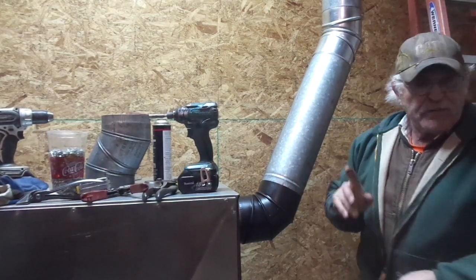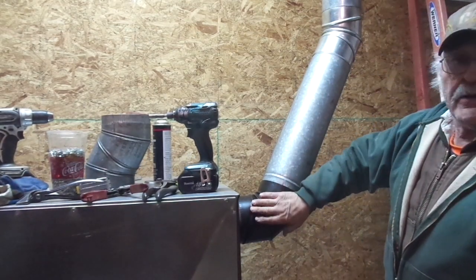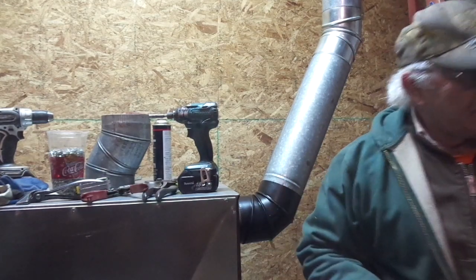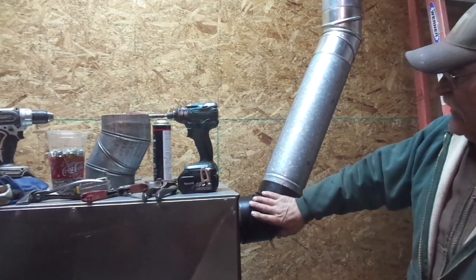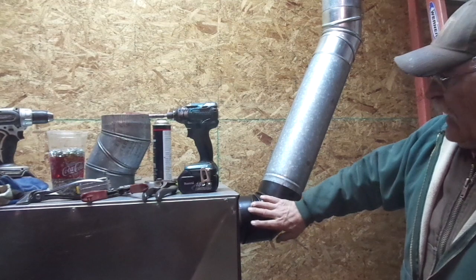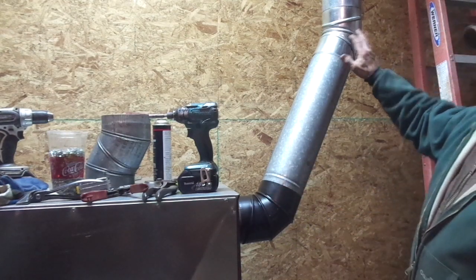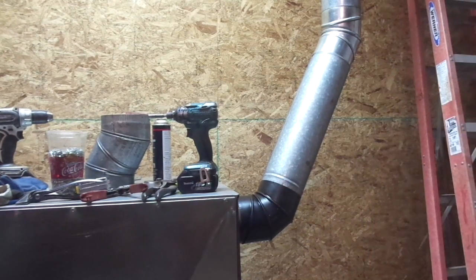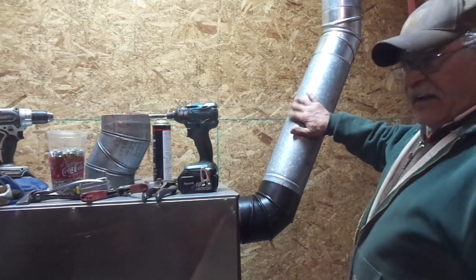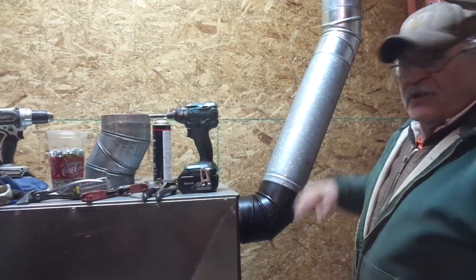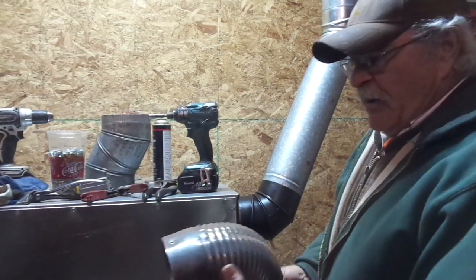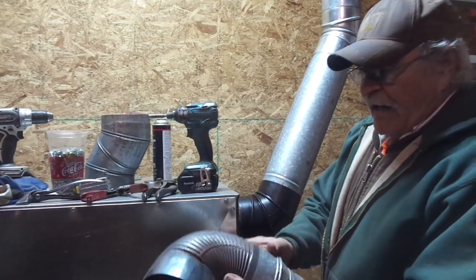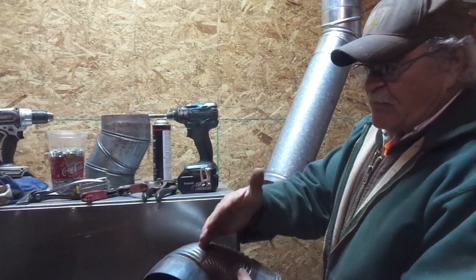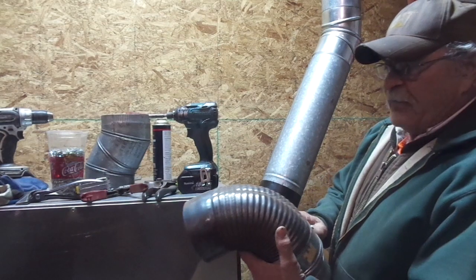Now, I do want to stress too that it's definitely not recommended to use these adjustable 90s. I think you can use the 26 gauge and 24 gauge black 90s, but definitely not the galvanized, simply because - remember I described the volatility of a flue fire if you're unfortunate enough to have one - they pretty much recommend this type of non-adjustable 90 or non-adjustable 45 in that particular case.